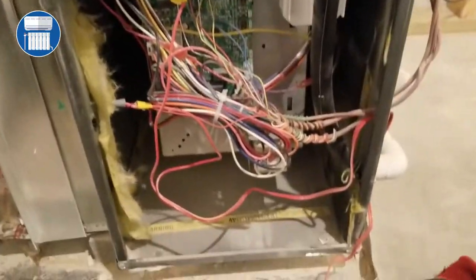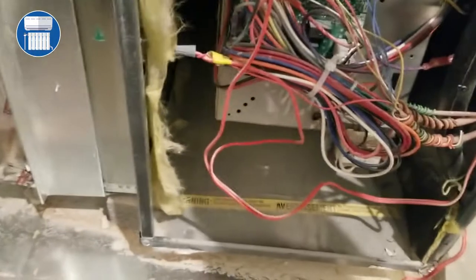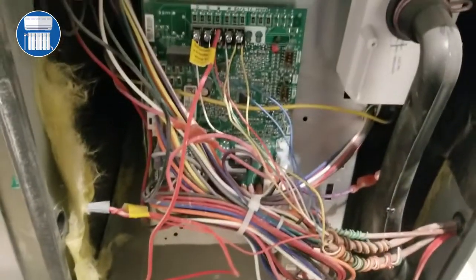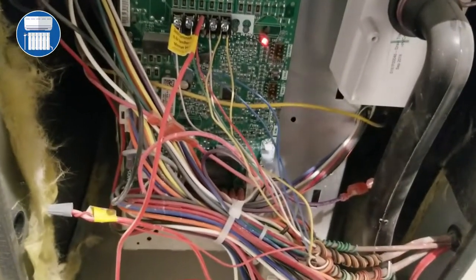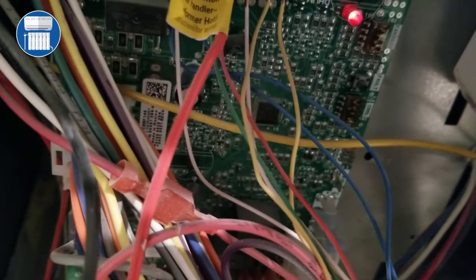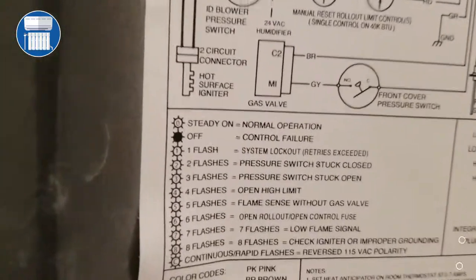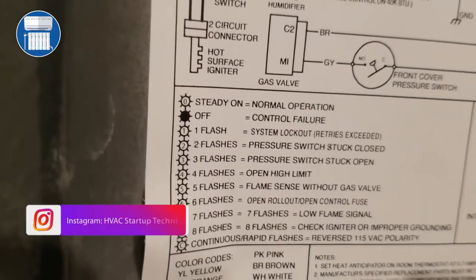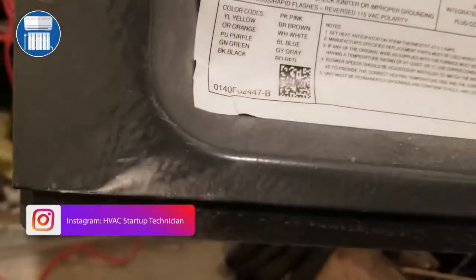So if you look at it, it says this light here. Once I turn this on, we will have a flash. Let me just zoom in on that light. If there's a problem with your furnace, this light is going to flash. So once you see that light flashing, that means you have a problem. You go to the back of this furnace board and you look at the flashes, and you see what it says here.